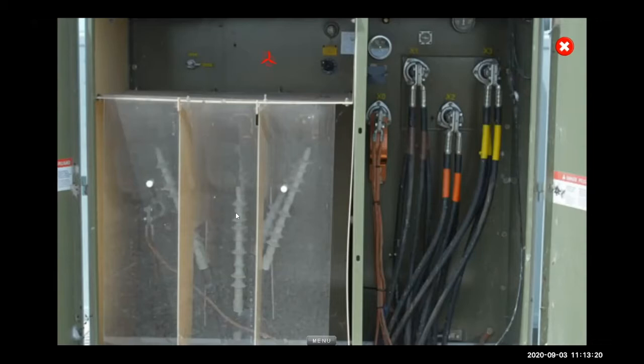So this transformer takes 575 volts and steps it up to 34,500. You'll generally see transformers go from 480 volts to like 12,470 volts. Then you'll see ones that do 13.8, and ones that do 34.5. They have all kinds of different voltages, but you'll start to see there's like 4 or 5 common ones. So 34.5 is very common, and 13.8 is very common.